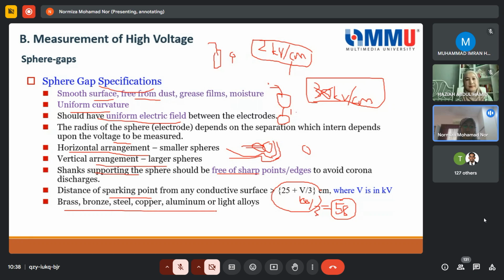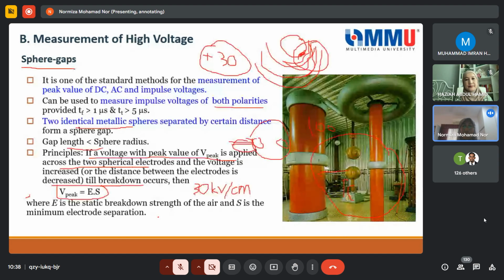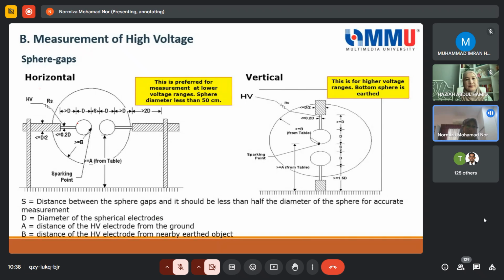Okay, so the typical material used, you can see here, these are the typical ones, but the one that you've seen in the example just now is brass or copper. Okay, so this is the construction of it. You have the horizontal arrangement and you also have the vertical arrangement. S is the distance of the spark gap, D is the diameter of the spherical electrode, A is the clearance, the distance of the HV electrode from the ground, and B is the distance from the nearby object.